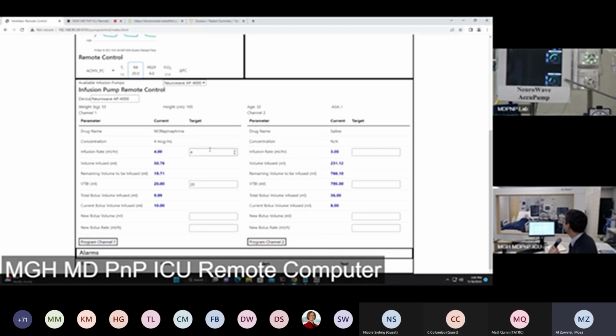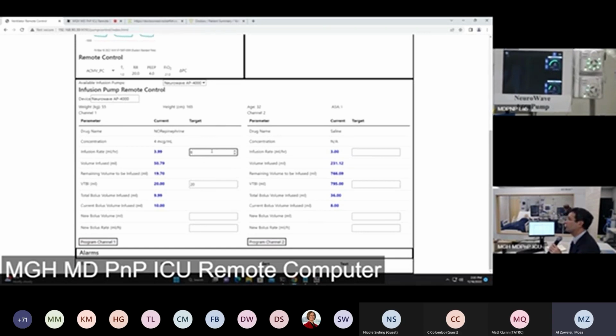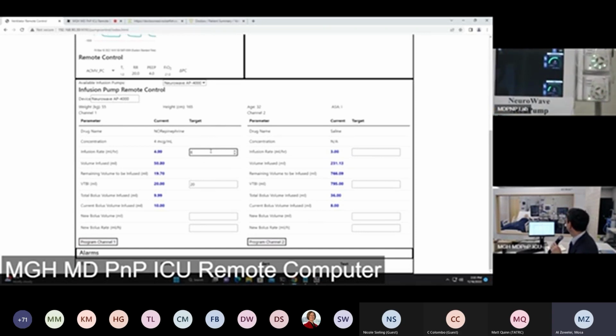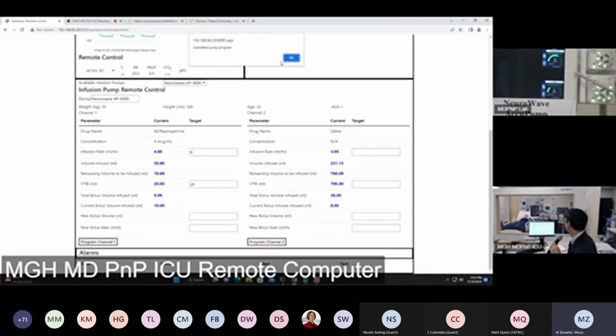I'll demonstrate controlling both. So first thing I'm going to do is double the infusion rate of the norepinephrine. I'm going to go from 4 milliliters per hour to 8. That's the top channel. You see in the center of the little circle there that it's running at 4 currently. Put in 8 here, put in the new volume to be infused, and click Program Channel 1. And that immediately changes to 8, and now it's delivering the drug at twice the rate.